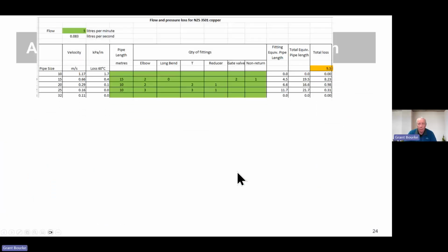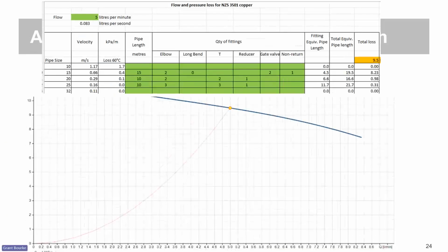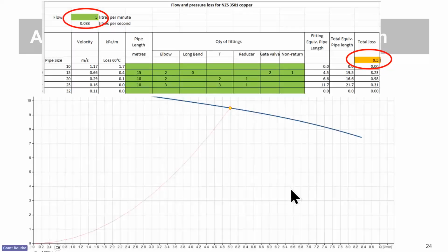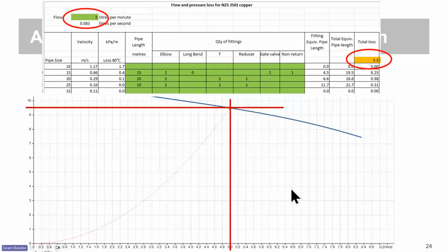So I had another couple of cracks at it, and what I found was that at 5 litres a minute, the pressure loss through my pipes is going to be 9.5 kPa, and lo and behold, at 5 litres a minute, my pump will do about 9.5 kPa. So what that means is if I put that pump in, note here also that I've allowed for a couple of valves either side of the pump and a non-return.